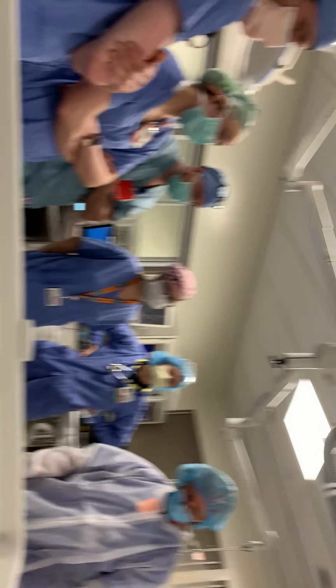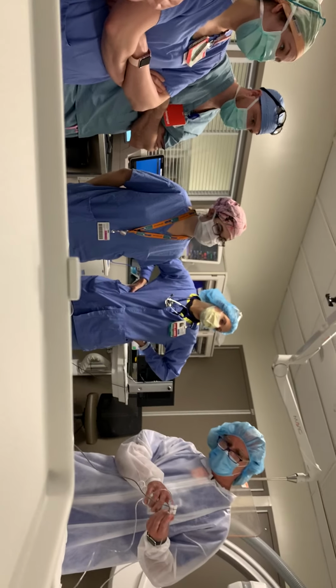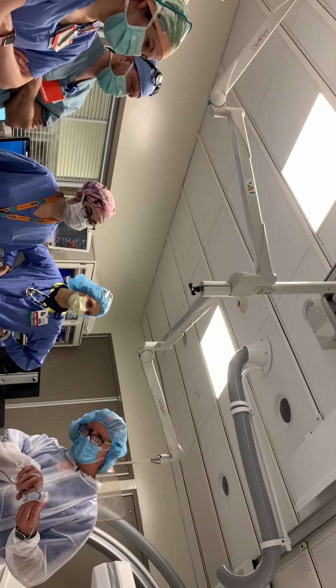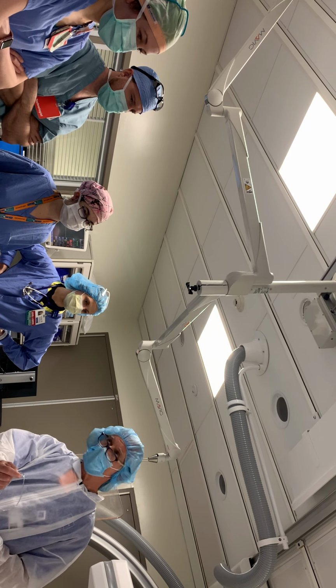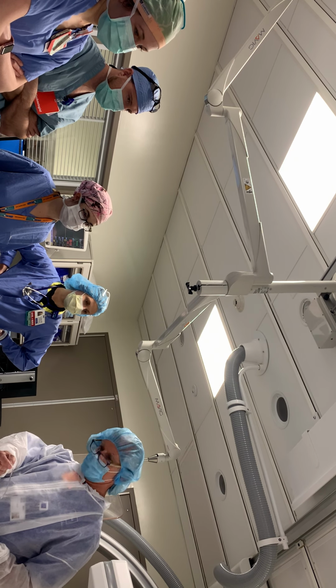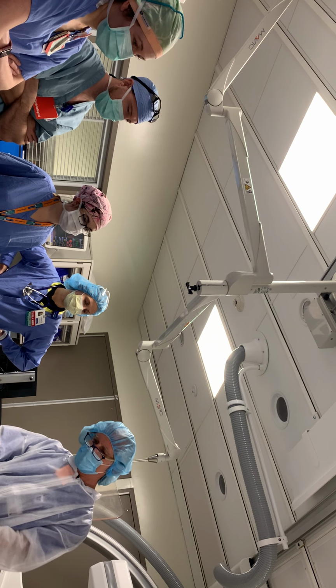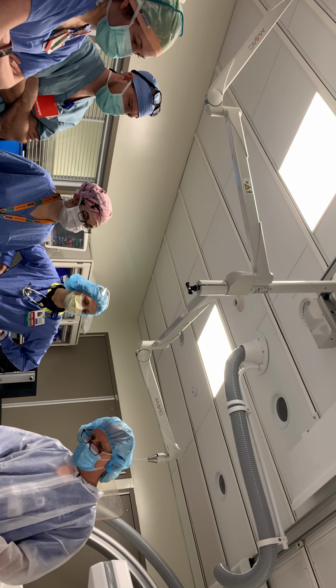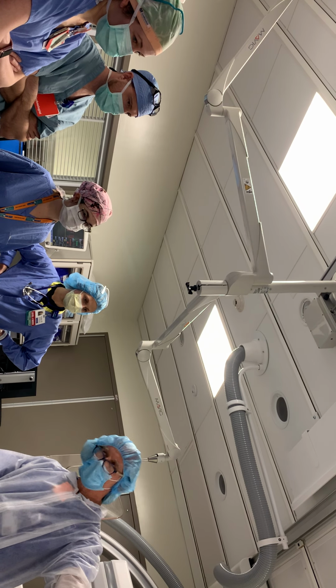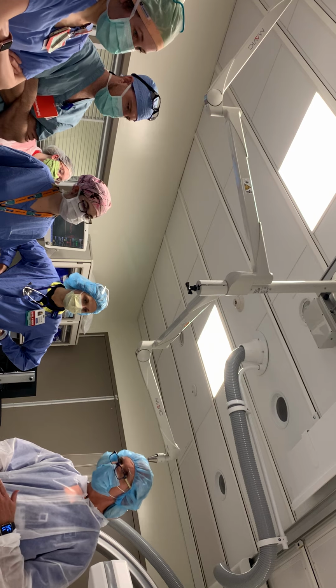Option B is our compensator version of an integrated transducer. The compensator has a flush port that doesn't come off the top, it actually comes off the bottom. And you connect what we call a compensating line, just a pressure line. So how does this one work different than the other one? This one, when you get ready to 0 it, you're going to flush out this port. You want to flush and fill that entire line with fluid. The purpose of that fluid is simply as a counterbalance.